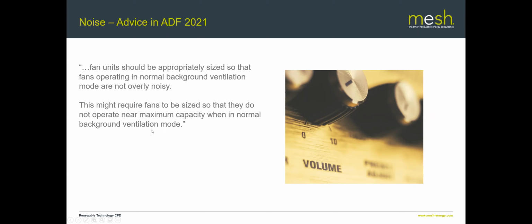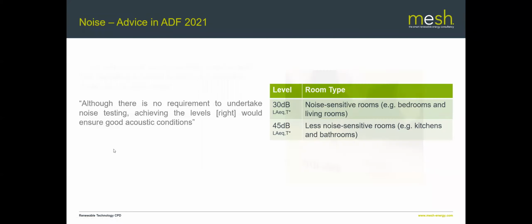Now, just taking that into what we actually do on a day-to-day basis when we're specifying these systems, what we find is that generally speaking, we want to be sizing the unit to be between a sort of background condition between 50 and 60% of full load, which means that you look at the sizing of these units and you think, well, that's quite a big unit, but actually when you plot it out, that could be quite easy to achieve.